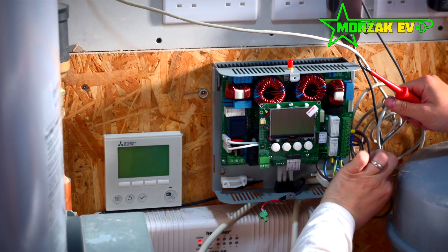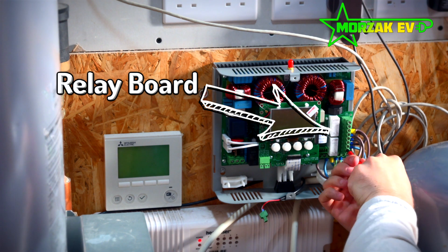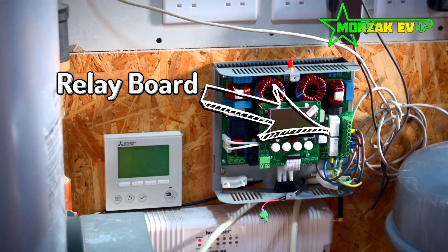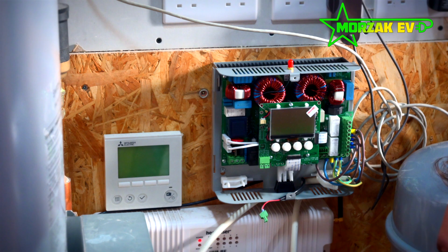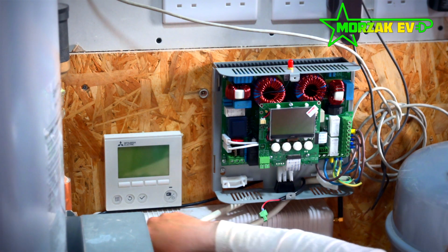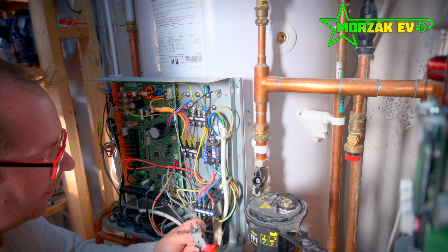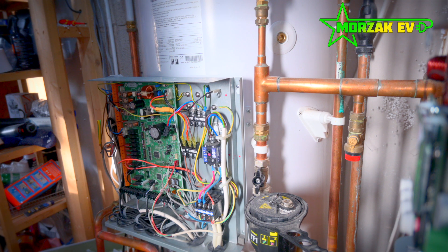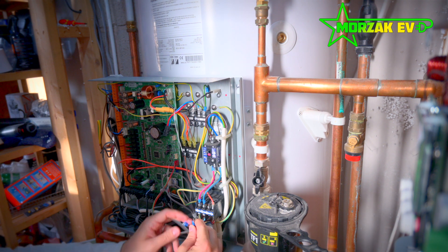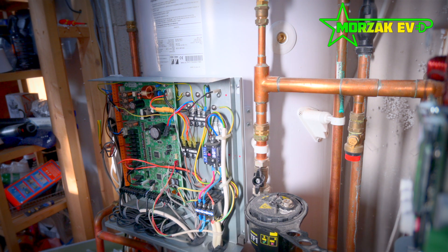When introducing the eddy, you need to make sure the Legionella cycle will still happen. myenergi also make a relay board, which you can use with the eddy to work with other devices. It's highly configurable, and there is a way of setting it up so that when the Legionella cycle kicks in, it completely bypasses the eddy and feeds the immersion heater directly. There's a little bit more detail in the installation process when you need to add the relay board, but it is possible.